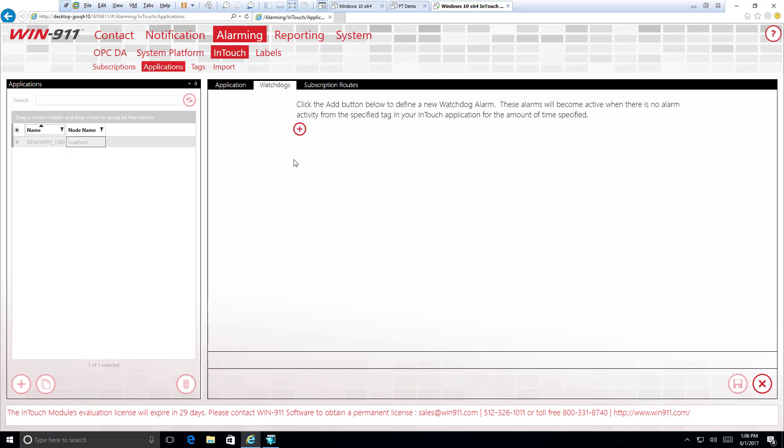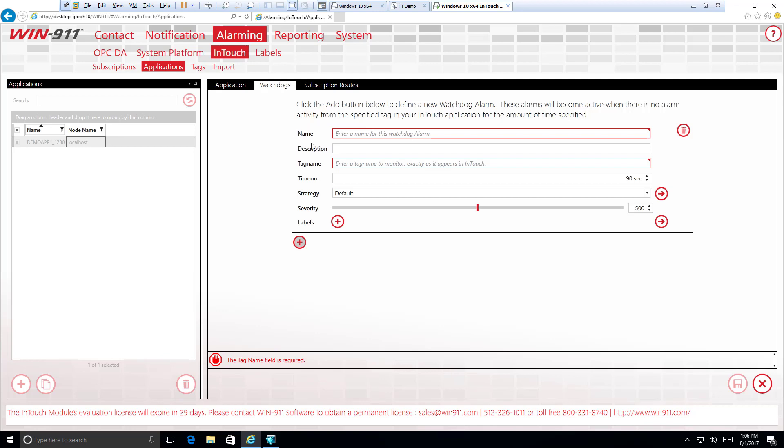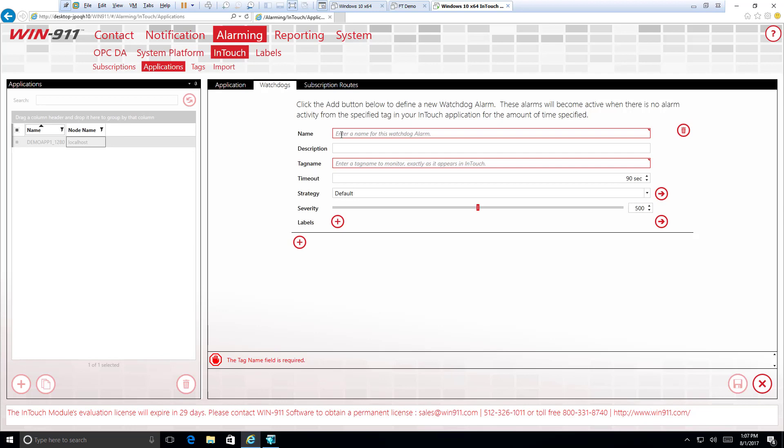Next one over, we have watchdogs. So watchdogs are a feature that Win911 developed in order to allow you to monitor the health or connectivity of your connection to InTouch. So the way we accomplish that is we have an alarm that is specified in InTouch that we connect to. And we will send an alarm not whenever this alarm goes off, but rather when this alarm stops going off. Basically, this watchdog will wait for a heartbeat, is how we often refer to it, from an alarm that goes off, say, every few seconds. This could just be a clock. A lot of people use a clock, and every time it ticks, you set a value that says set off an alarm every time this value changes. Well, of course, the clock keeps on ticking away, and you'll receive an alarm every one second. And as long as we're seeing those alarms, we know that we are connected and good to go.